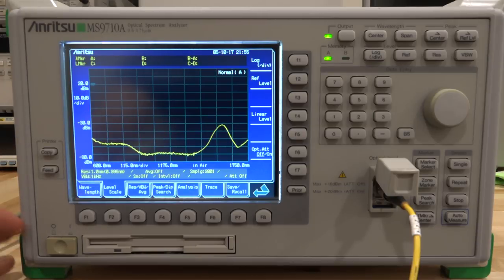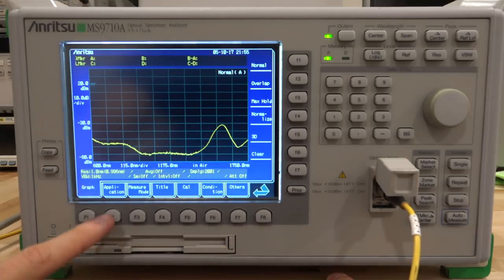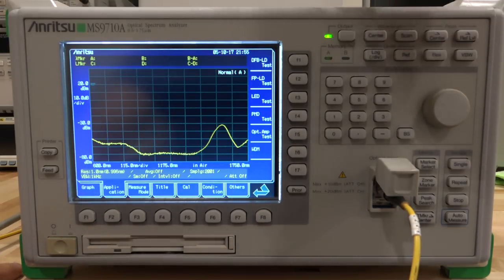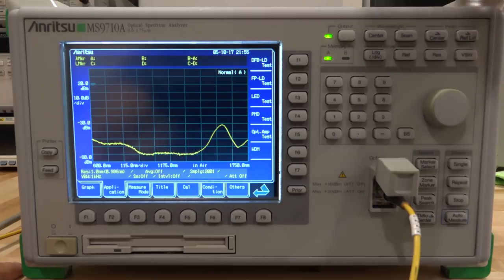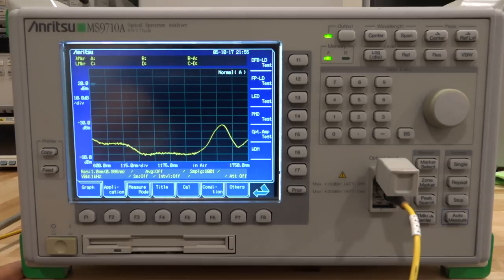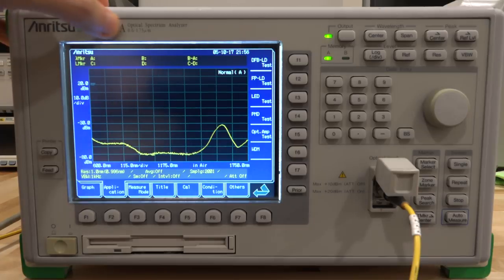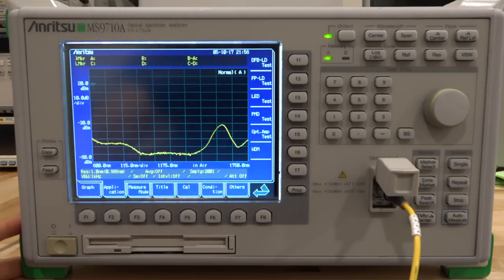But this is loaded with a lot of interesting applications. For example, under the applications, you can do FP laser diode test, LED test, PMD test, which is polarization mode dispersion, optical amplifier test, WDM, wavelength division multiplexing. Very cool. Fabry-Perot laser, lots of cool stuff you can measure and test, and it gives you all of that built into it. Definitely capable. Fantastic. It's the A revision. There are now many other revisions after this. But for its compactness and for how awesome it works, I'm really happy with it.